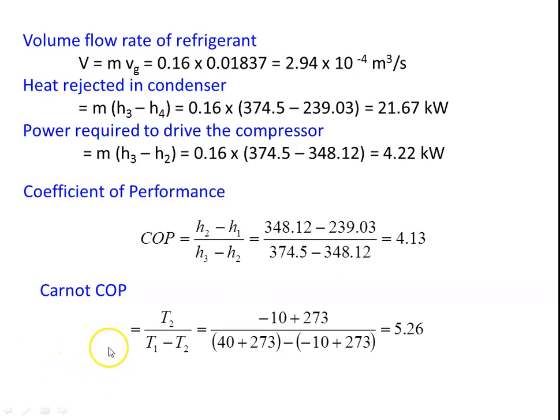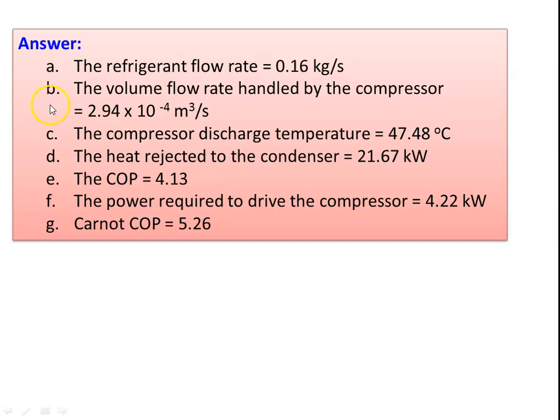The Carnot COP based on temperature = TL / (TH - TL) = 263 / (313 - 263) = 5.26. The vapor compression cycle COP = 4.13. Answers: refrigerant flow rate = 0.16 kg/s, volume flow rate = 2.94 × 10⁻⁴ m³/s, compressor discharge temperature = 47.48°C, heat rejected in condenser = 21.67 kW, COP = 4.13, power required = 4.22 kW, Carnot COP = 5.26.